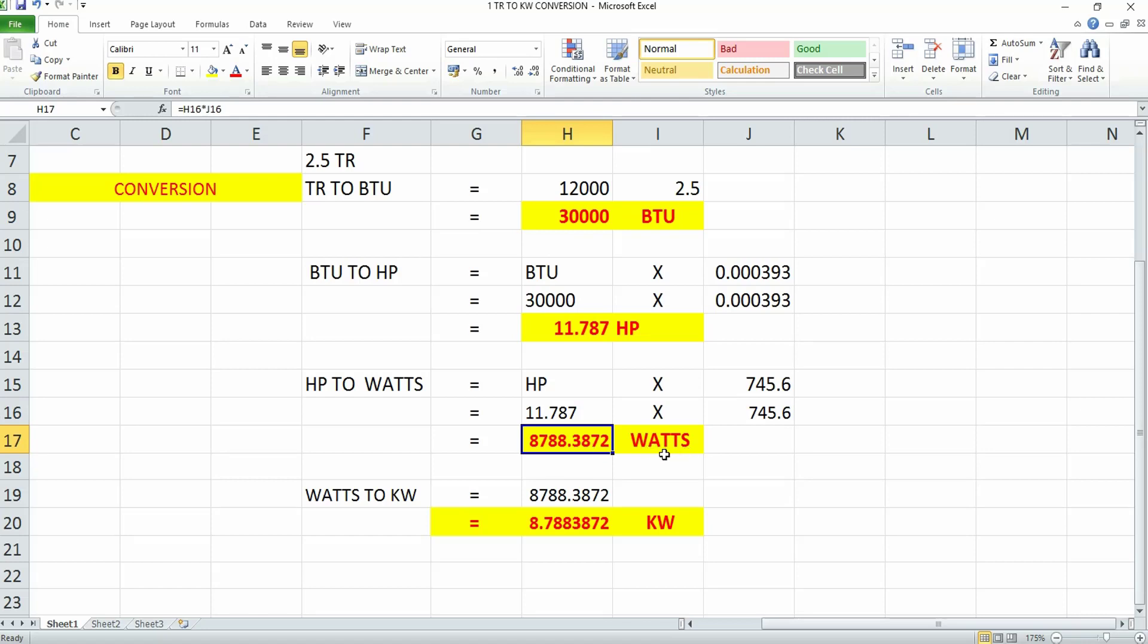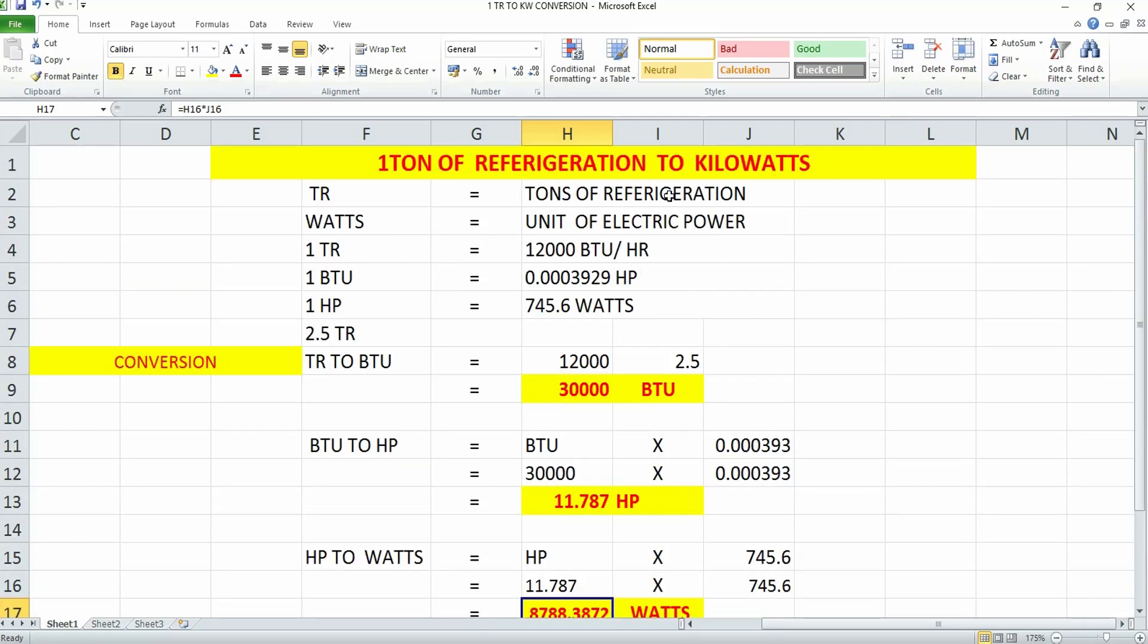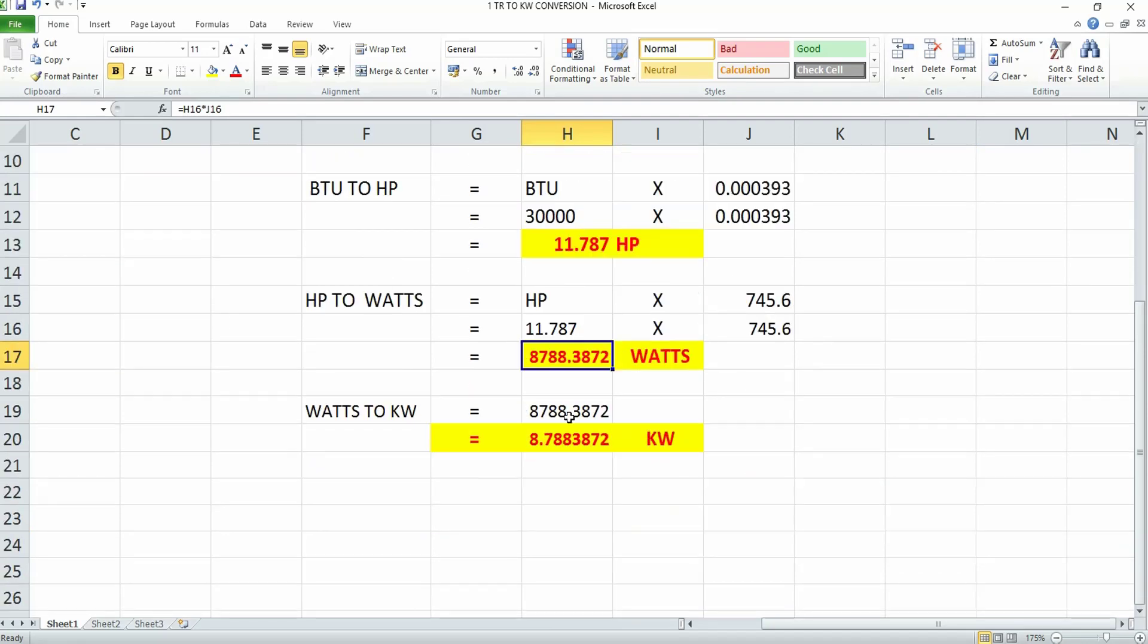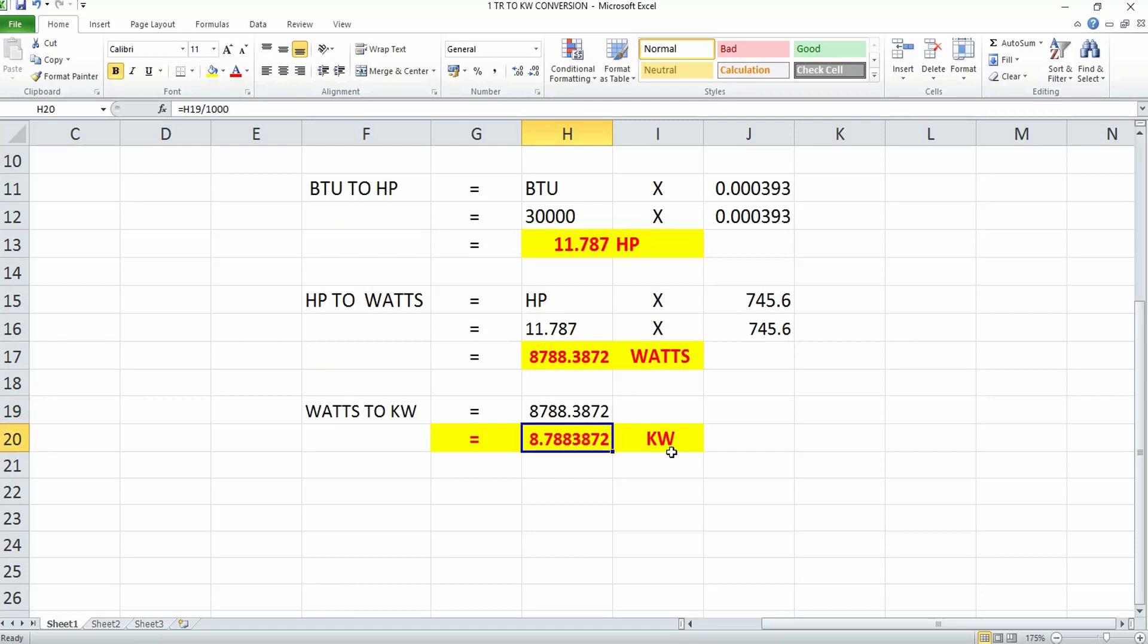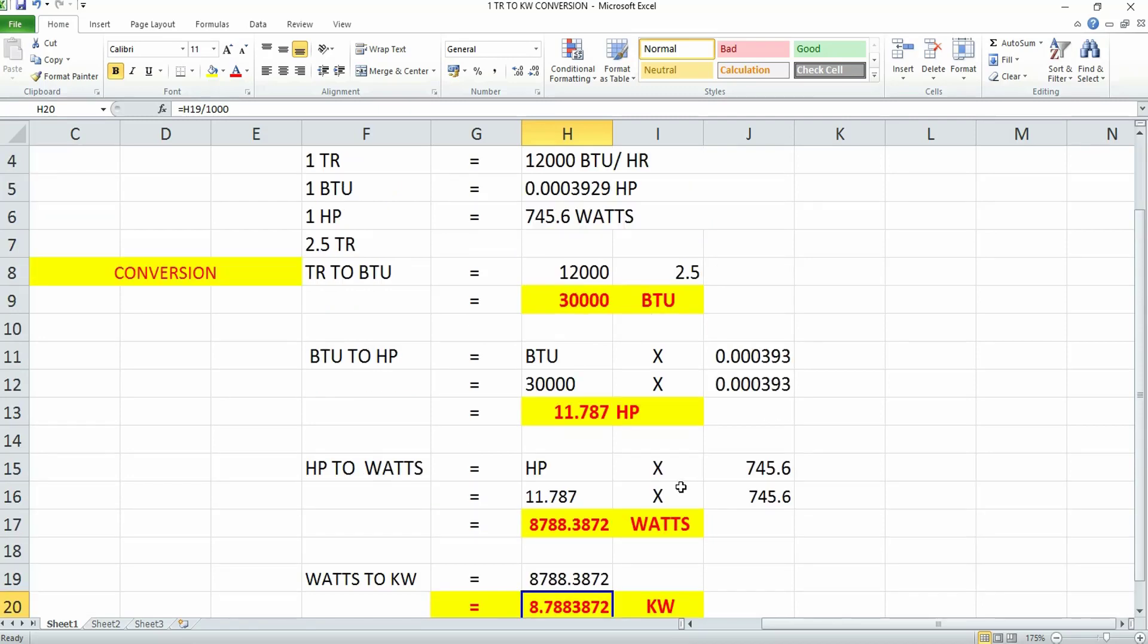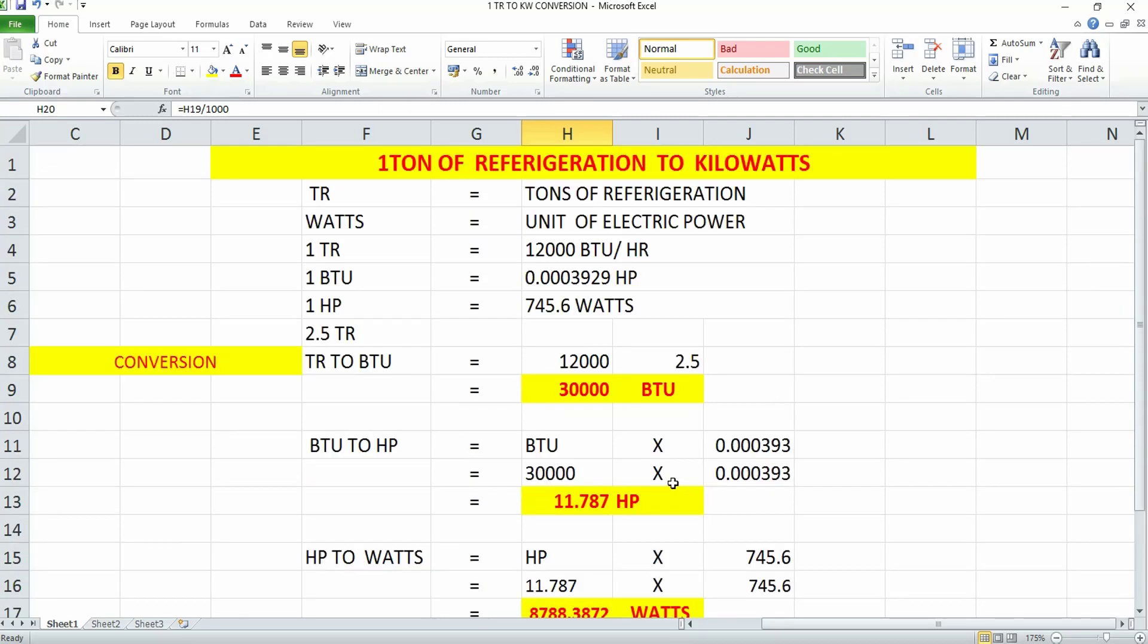This is your HP converted to watts. Our main intention is to convert TR to kilowatts. As you know, one kilowatt is one thousand watts. If you divide 8788.38 watts by 1000, you get the power in kilowatts. This is how you convert tonnage of refrigeration to kilowatt.